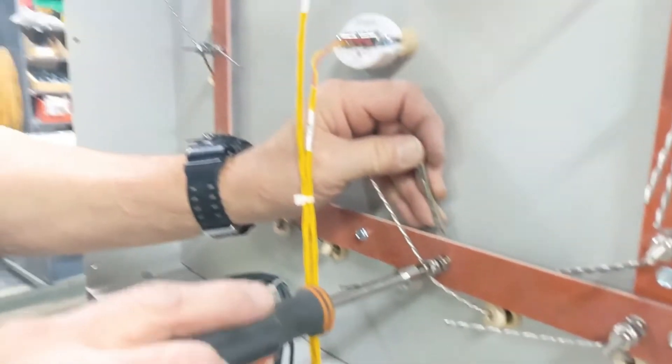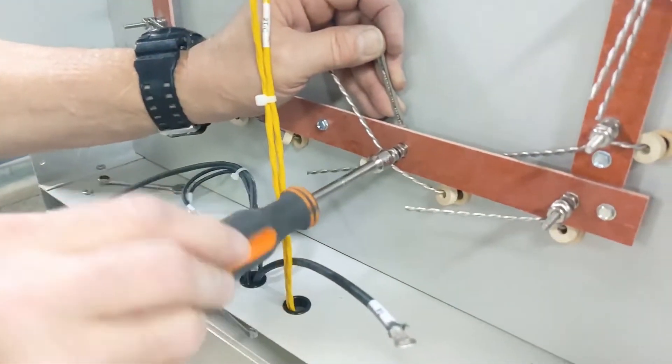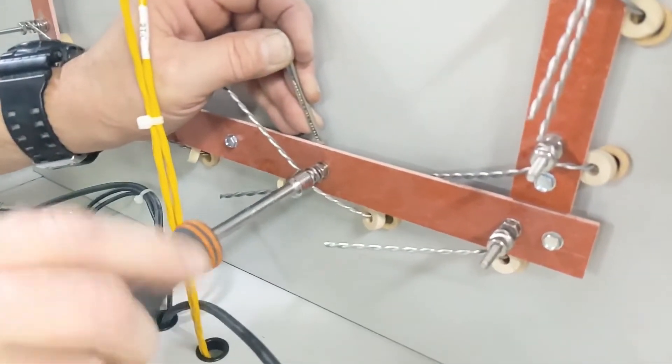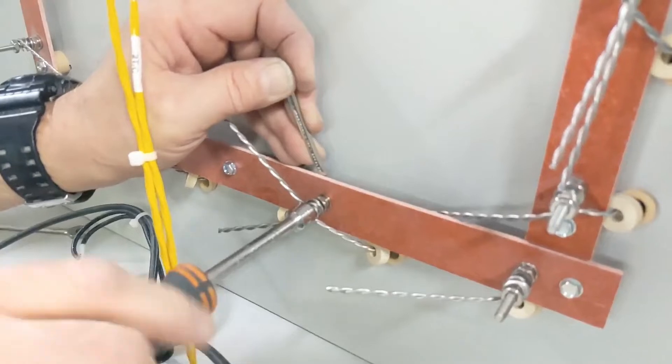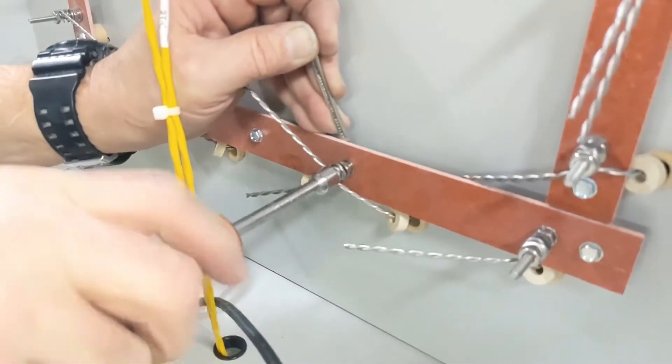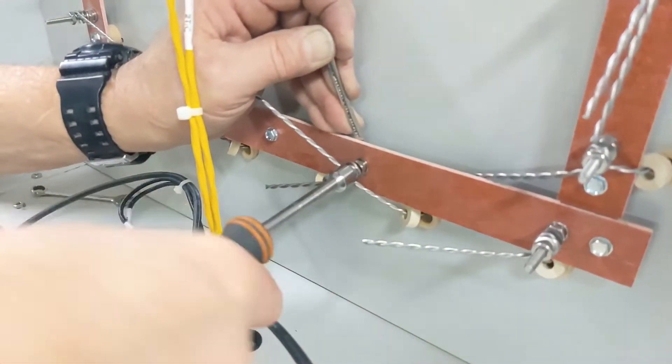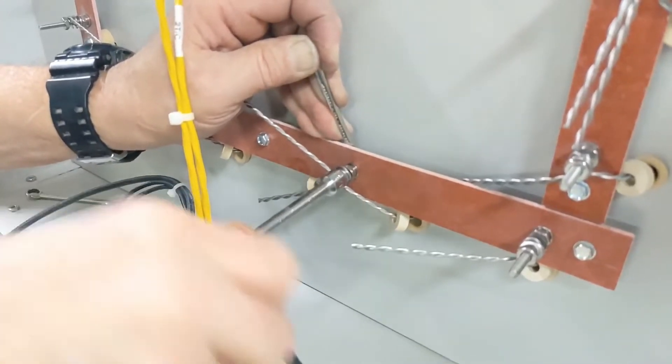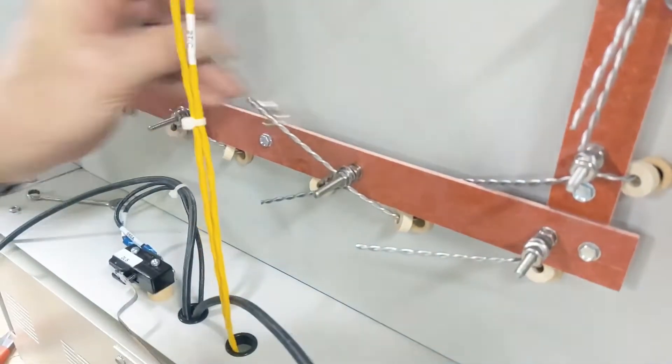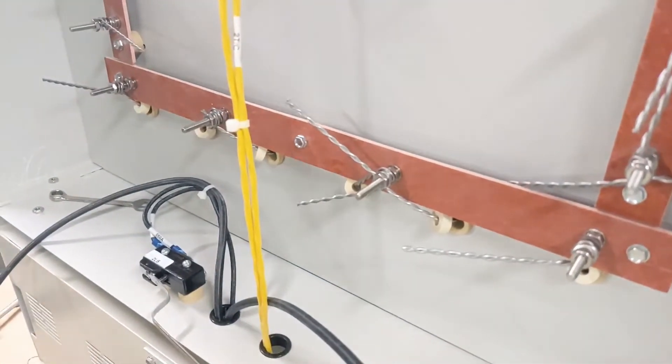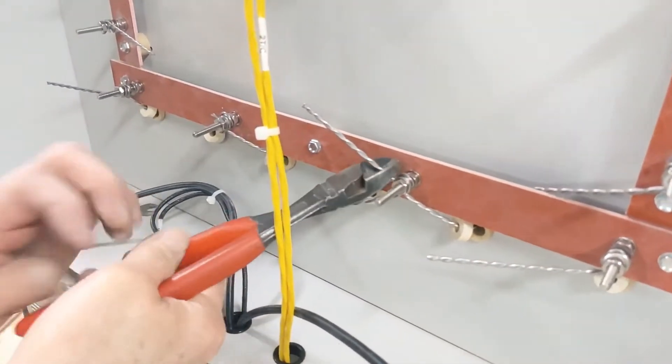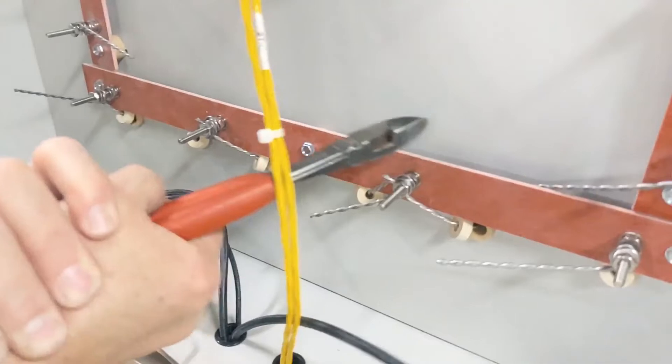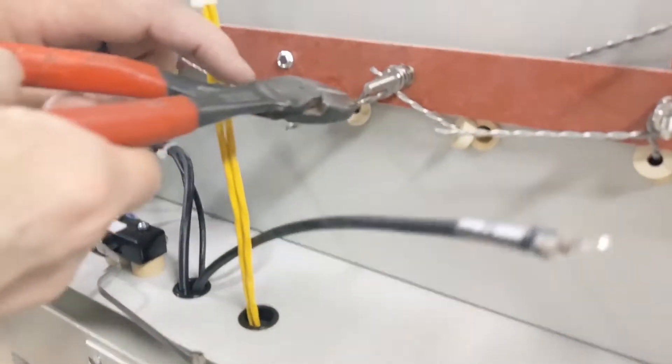Just showing the tightening procedure again. 5/16 wrench on the hex nut head behind the terminal board. 5/16 nut driver to tighten down the hex nut. You want to go about a half turn past hand tight. And then diagonal cutters to snip off the element tail.